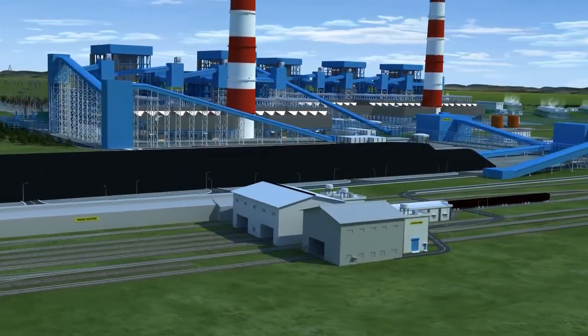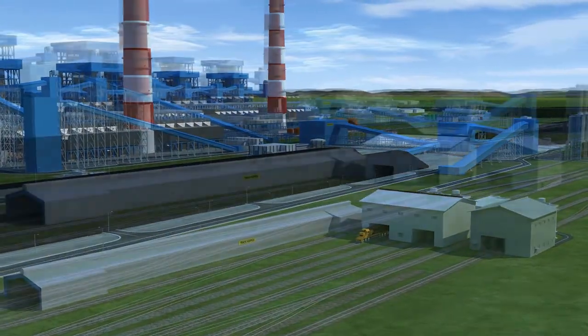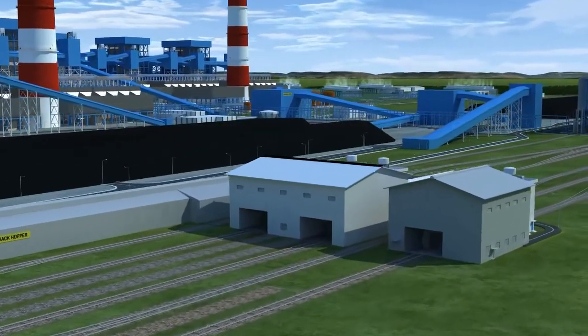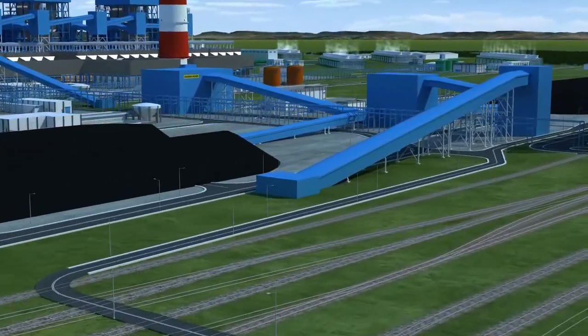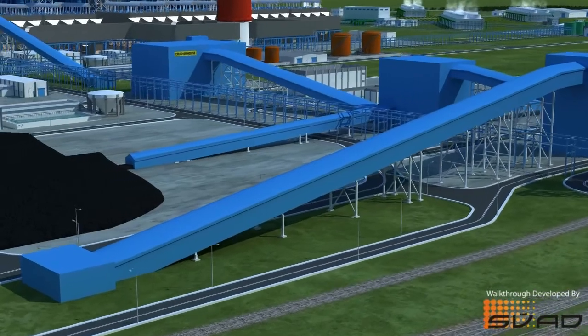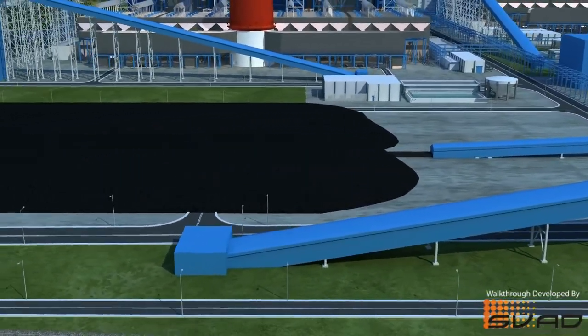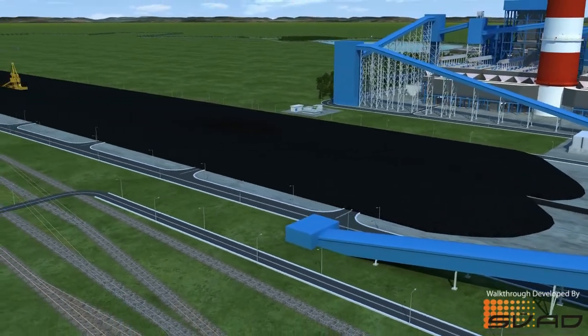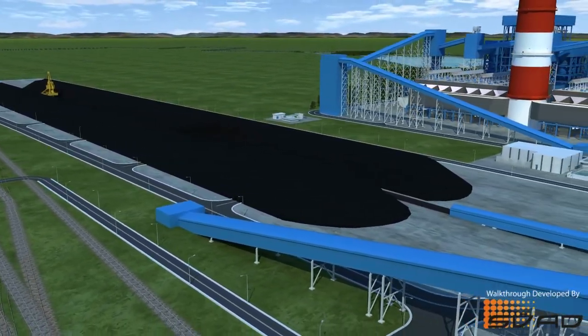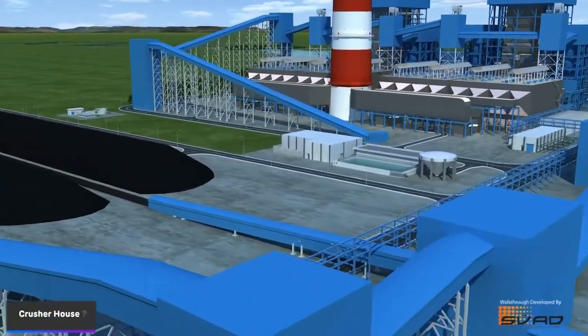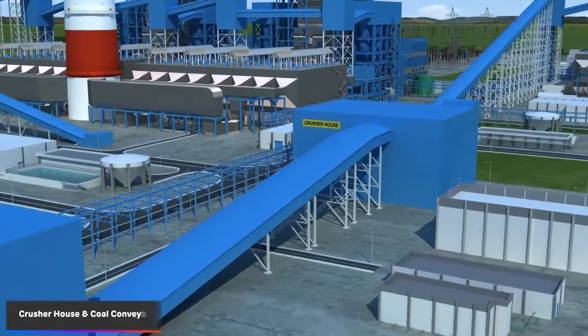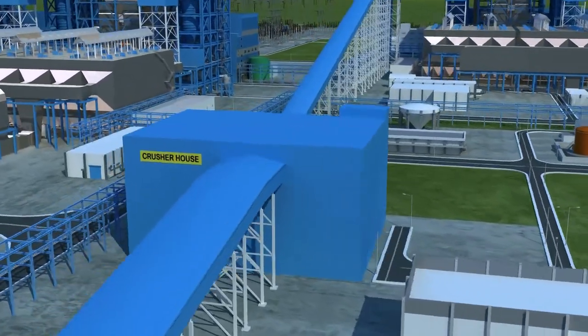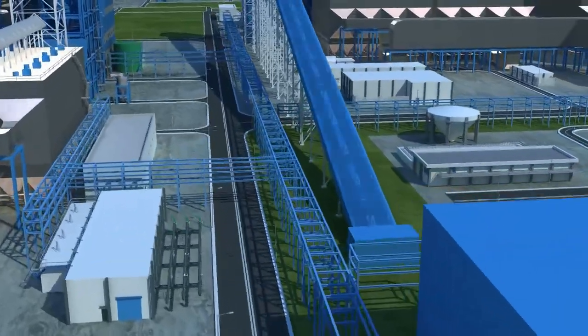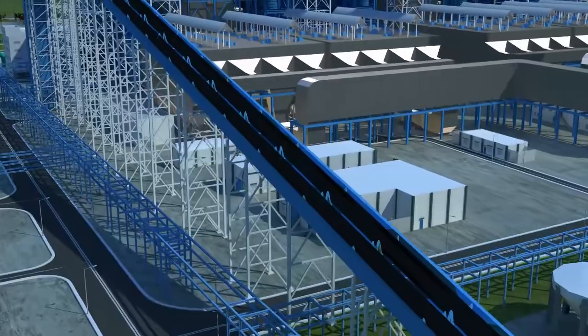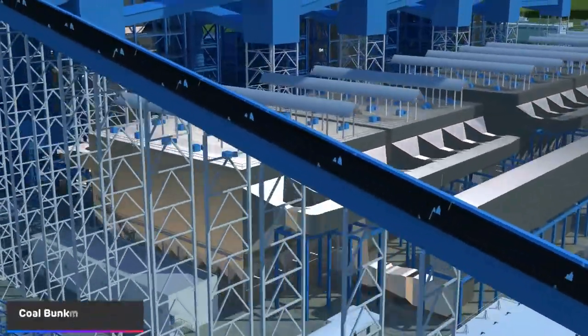The coal handling plant has been supplied by Messrs. Larsen & Toubro Limited. The coal will be unloaded through a track hopper and 4 numbers of wagon tipplers. The coal is then further conveyed either to the stockyards within the plant or to coal bunkers of various units. Facility to store around 7.2 lakh metric tons of coal, which is about 15 days' stock, is made through 2 stockyards. Coal passes through 6 numbers of crushers, each of 1,250 tons per hour, installed in a single crusher house. The coal is fed to coal bunkers of different units before entering the milling system via coal feeders.